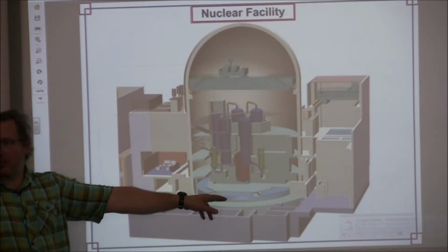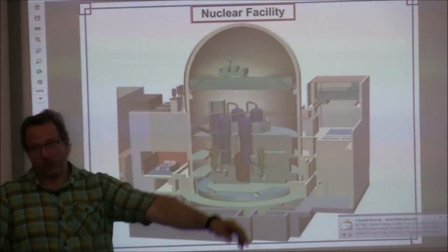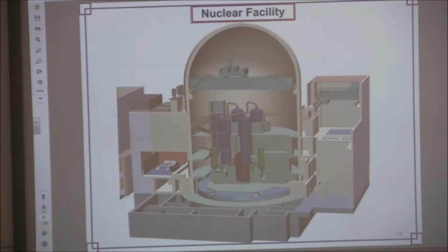That can reduce some of the energy, right? Because if you have cold water, you can see that. Some of the older facilities actually had ice with boron at the top. So if you had big blocks of ice and you kept it cool until you had an accident, well, if you get something at 550 degrees and something that's at minus 20 degrees, you can absorb a fair amount of energy with ice. So they would put it on the top, it would melt the ice, and that would absorb some of the pressure, reducing the size. That's not a lot of plants because that's a maintenance issue. So that's the traditional design.